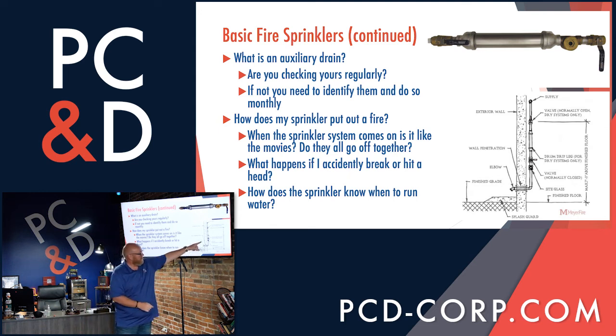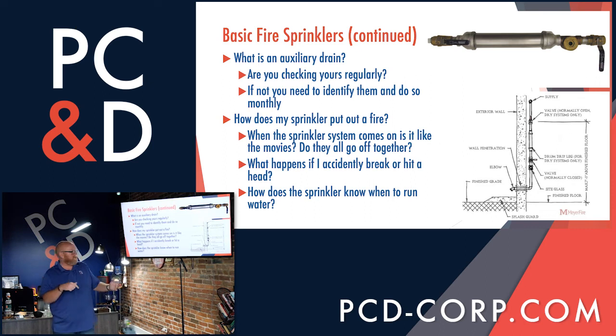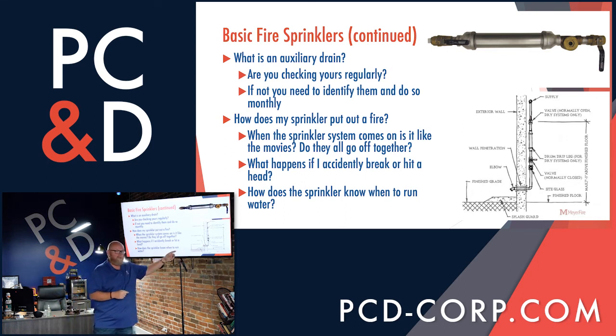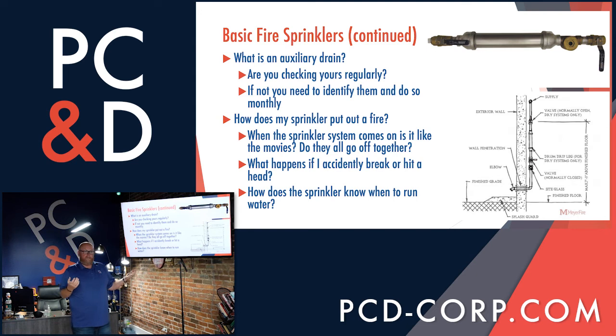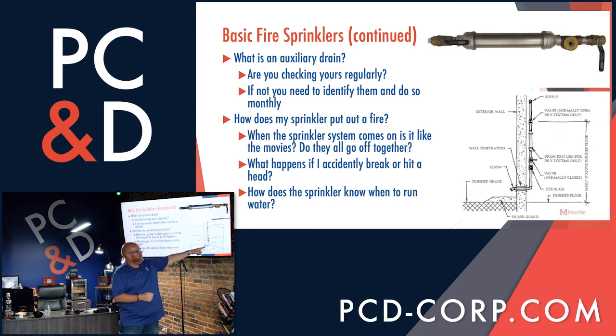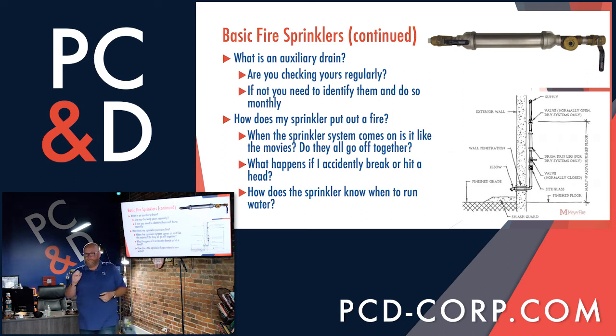And you're basically going to see an elbow sticking through your building, either on a galvanized piece of pipe or black iron piece of pipe, and a lot of times they'll have a 45 turned at a slight angle coming out the wall. If you've ever walked the perimeter of your building and saw this black iron or galvanized pipe coming through the exterior of your building at a 45, and you've always thought, I wonder what that is, that's your low point drain. So walk the perimeter of your building, look for these low point drains. When you identify one on the outside of the building, notate that and think, there's a med room right inside the wall there. Or, that's my mechanical room where my water heaters are on the 200 hall. Wherever it may be, go back inside your building and look for this setup to where you've got your low point drains.